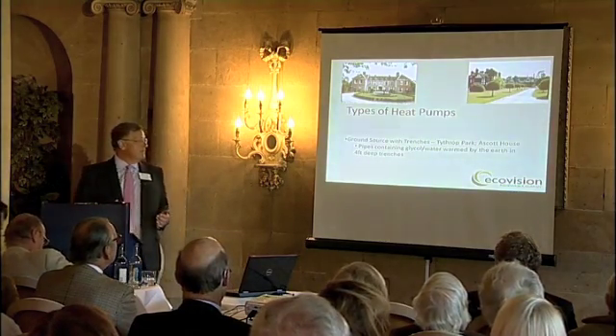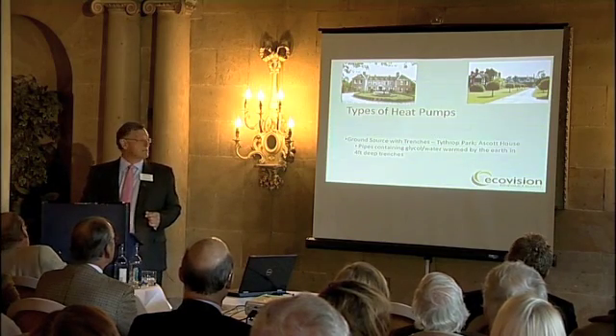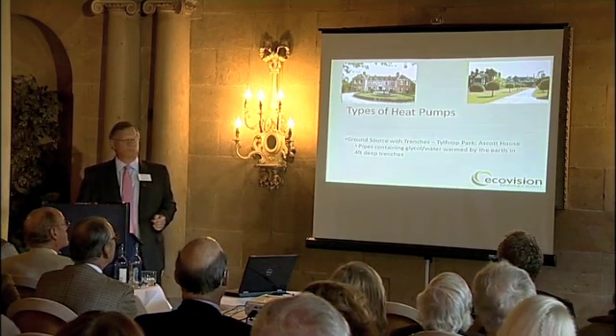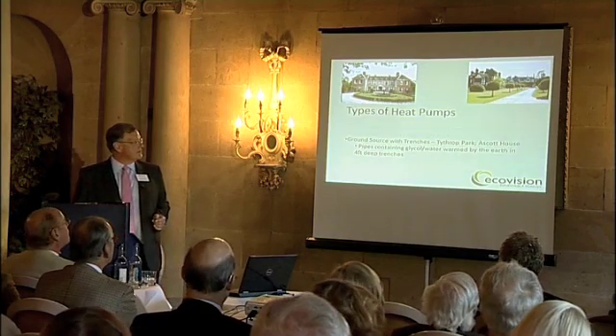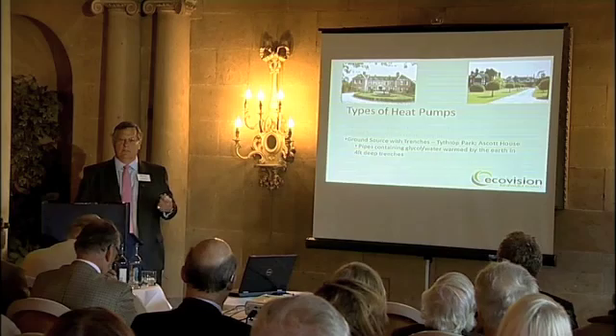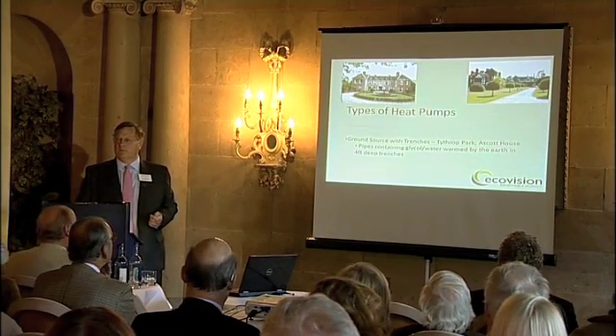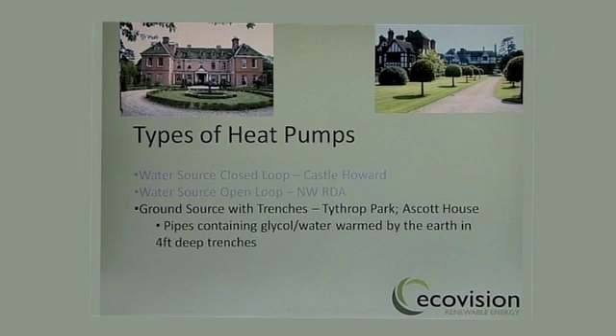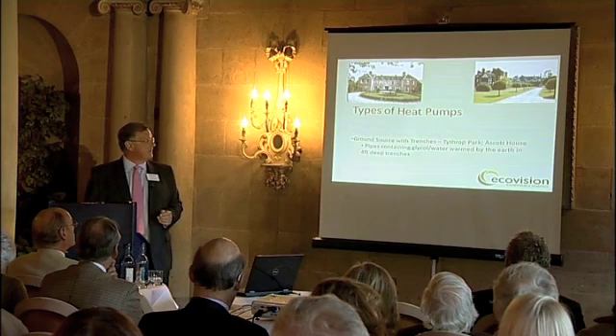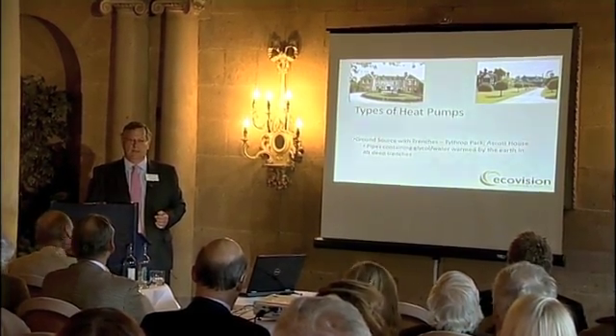Ground source heat pumps, which we use more often for large country houses, take advantage of large acres of land using trenches. One example is Tythrop Park in Oxfordshire; another is Ascott House, a Rothschild National Trust house in Bedfordshire or Buckinghamshire. Rather than extracting heat from water, you're extracting it from the ground via trenches about four to five feet deep with pipes in them. Once filled in, you never touch them again — they last about 100 years, and the heat pumps last about 25 years. Trenches are preferred over boreholes as they tend to be less expensive.